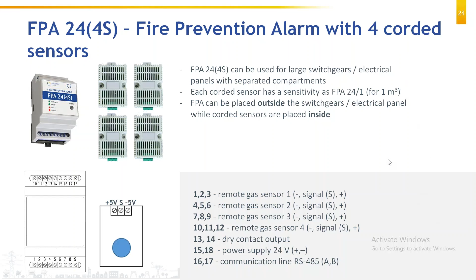When I go to the more detailed diagram, we will see that these points in this particular slide we have already discussed. FPA detects the content of carbon dioxide in the protective volume. Gas concentration when only one FPT is triggered is around 980 ppm. The triggered threshold for FPA is 250 ppm. Got my point? So if some of the gas escapes because of the holes in the panel or because of the opening for incoming of bus bar or cables, no issues. Your FPA will still sense because it has a sufficient volume of gas available. Thresholds are needed to prevent the sensor from triggering from other gases. So your FPA will not detect any other gas, but it can detect products of combustion of cable insulation. As I mentioned some time back, if your cable insulation starts burning, your FPA will detect that also.